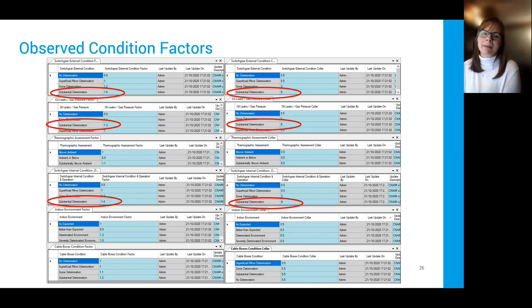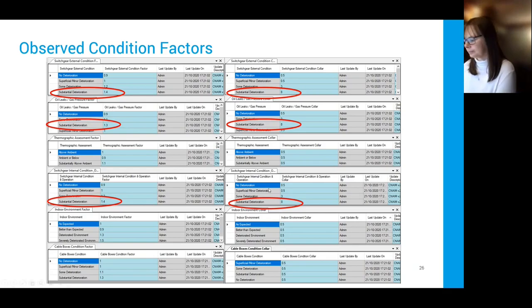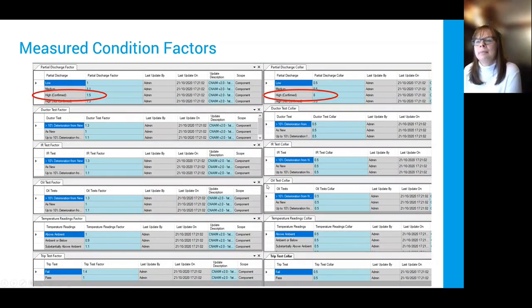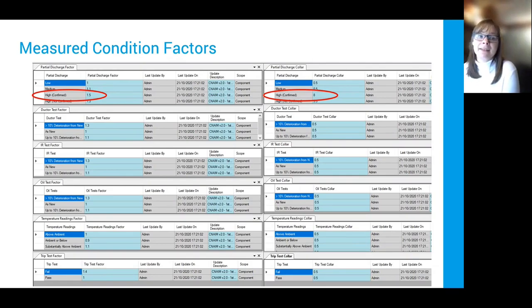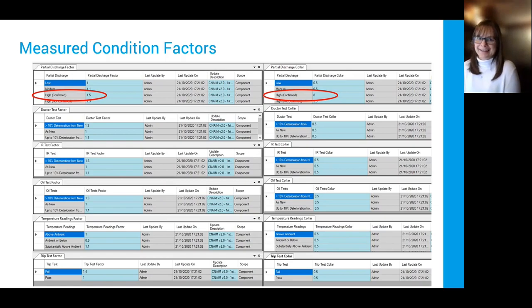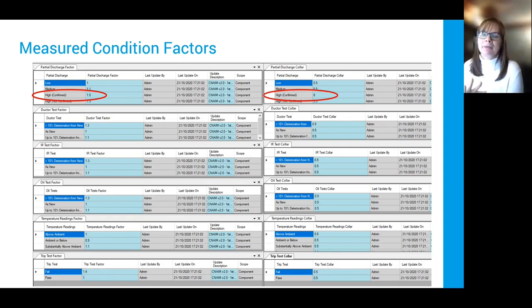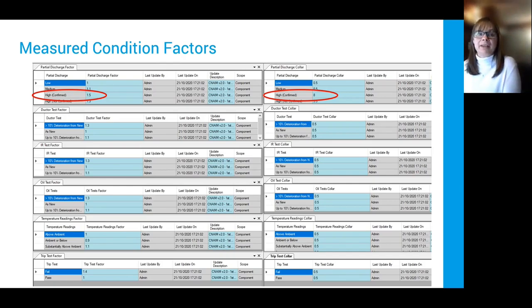Looking at which priorities are highest — the ones with the highest factors — in common methodology those are external condition, oil leaks, gas pressure, internal condition, and operation. If you collect any pieces of information, these are the ones valued most. Any time you visit a substation or site, it's worth looking for opportunities to collect this data. For measured conditions, the one with the most impact is partial discharge — not really a surprise for switchgear, as many assets fail due to partial discharge. If you're going to do any test on switchgear, partial discharge testing is the one to do.